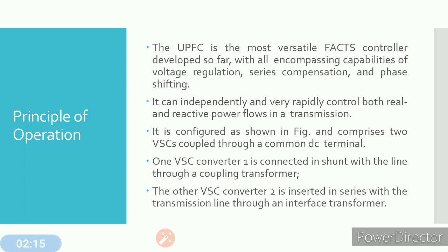The UPFC consists of two Voltage Source Converters (VSCs). One is known as the series converter and the other is known as the shunt converter, and both are coupled with the help of a DC terminal. Converter one, which is connected in shunt, works like a STATCOM and is connected in shunt with the help of a coupling transformer.